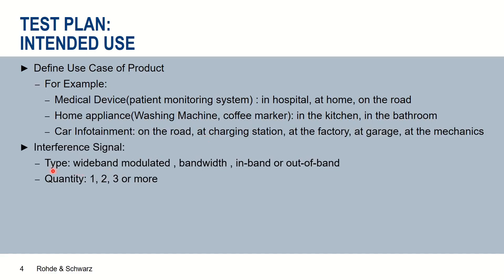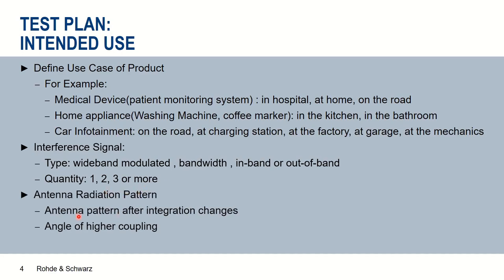The second part of the intended use module is to understand the different types of interference signals to use. They are normally wideband modulated signals with wide bandwidth. We need to consider what bandwidth to use and place them as in-band and out-of-band interferences. We also need to understand the number of interference signals we want to test our product with, and finally understand the radiation pattern characteristics after integrating the antenna module — requiring an antenna characterization measurement on the finished product.